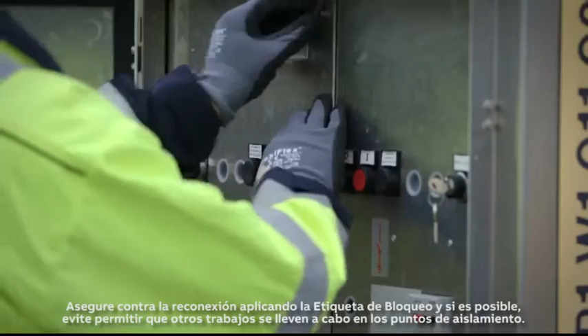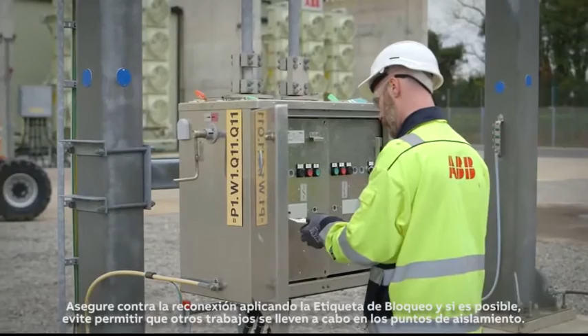Step 3B. Secure against reconnection. Secure against reconnection by applying lockout-tagout and, if possible, avoid allowing other work to take place at the points of isolation. If there are multiple points of isolation, group lockout-tagout shall be implemented with the person in charge of work, or PICW, acting as the group lockout-tagout leader.